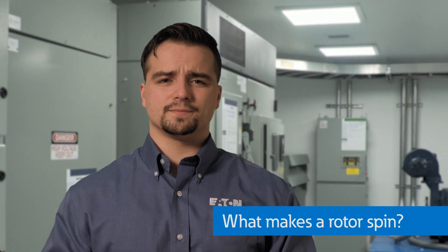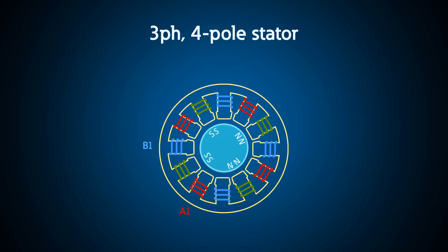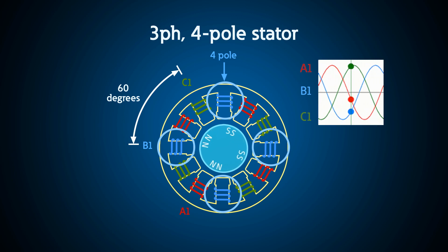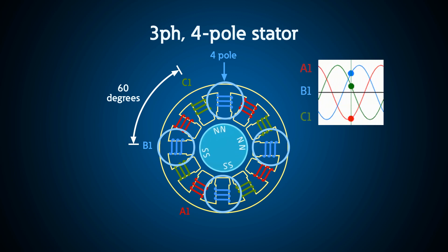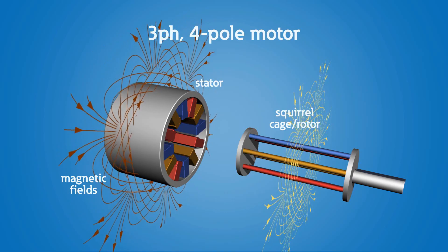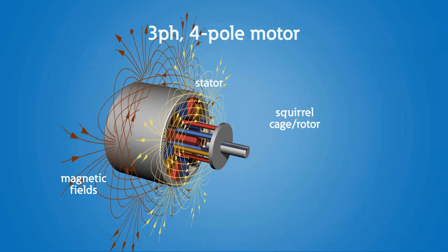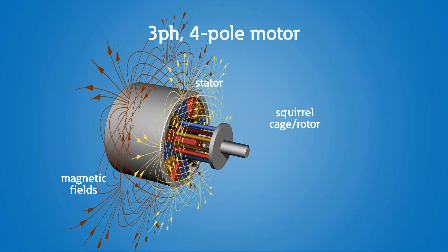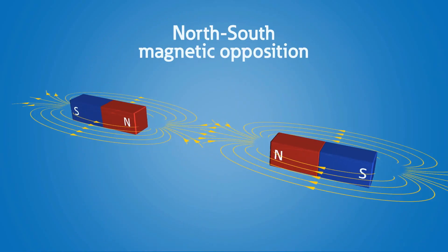But first, what makes the rotor spin? For a three-phase motor, the electric power energizes the three stator coils, one for each phase. These coils are evenly spaced around the stator 60 degrees apart for a four-pole machine. Three phases alternating 120 degrees apart electrically results in a rotating magnetic field. This magnetic field induces a current on the conductive squirrel cage rotor — this is where the induction motor gets its name. The current that flows through the squirrel cage produces a magnetic field that opposes the magnetic field produced by the stator windings. These magnetic fields oppose each other just like the north poles of two magnets, but because the fields are spinning, we get a rotation in the rotor.